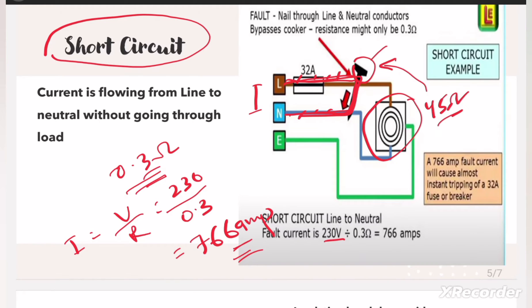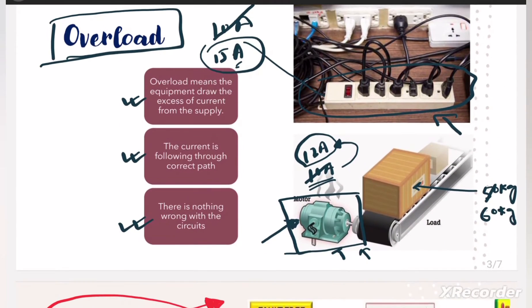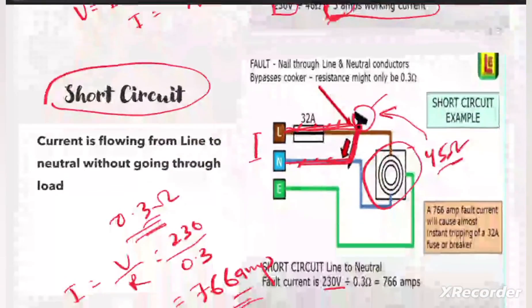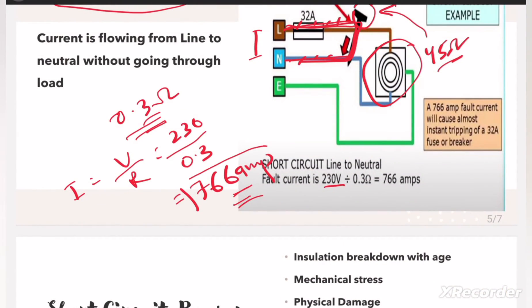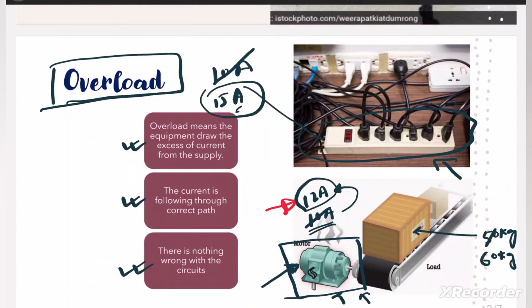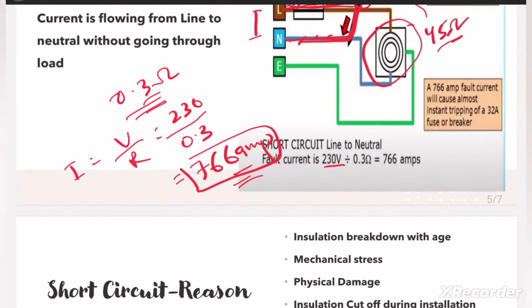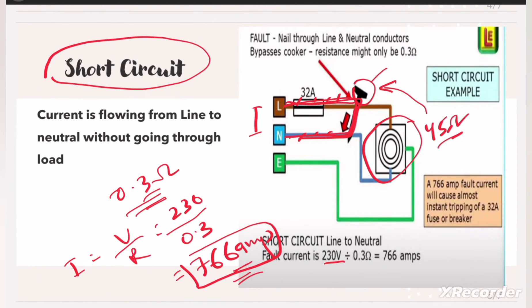So far we observe that in the overload condition there is excess current, and in the short circuit condition there is also excess current. However, the excess current in short circuit is 10 to 100 times more than the rated current, whereas in overload it is just a fraction more — for example from 10A to 12A or 10A to 15A. In short circuit the abnormal current is several times higher than the rated current.